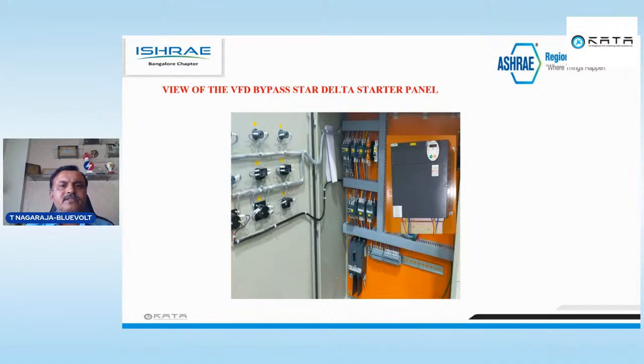Then VFD bypass star delta starters. In the same way, a VFD bypass star delta starter is also a 6 contactor. Some people will use 5 contactors, since they don't want to use the VFD input, so 1 contactor can be saved. But again, for the safety of the VFD, we have to use 6 contactors.